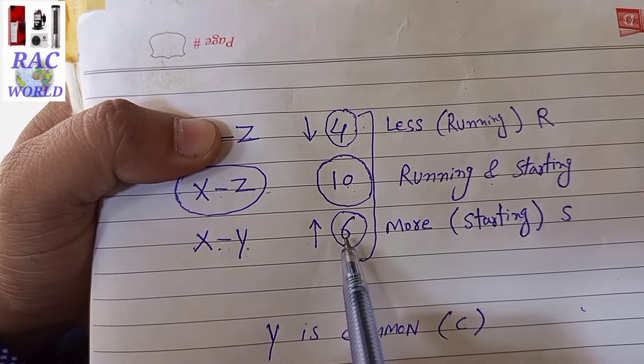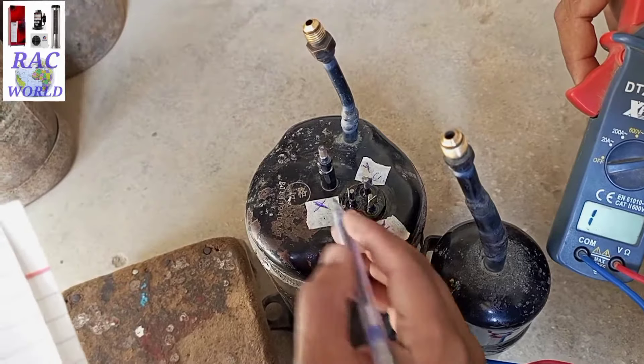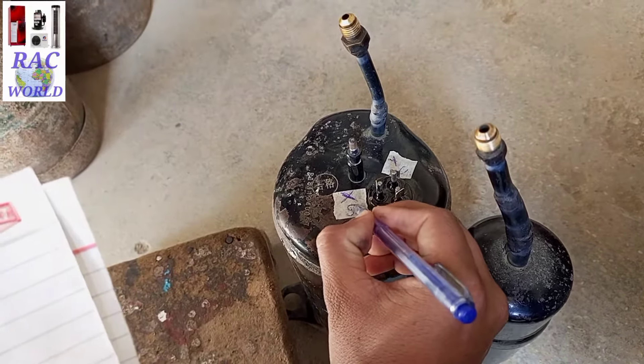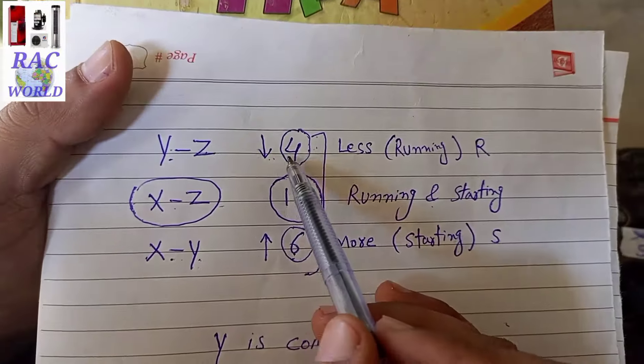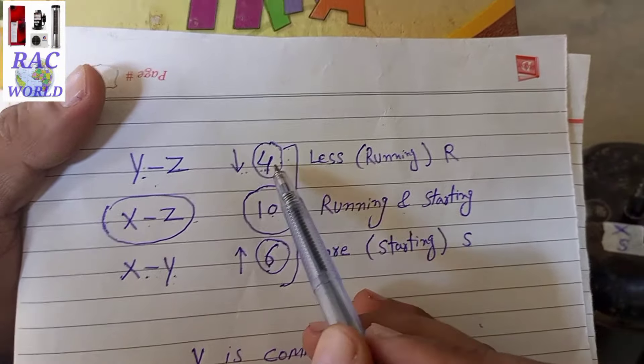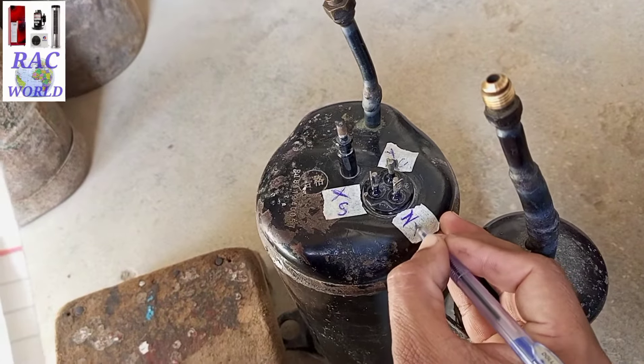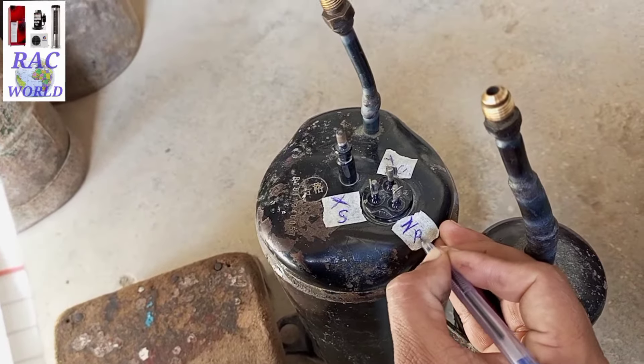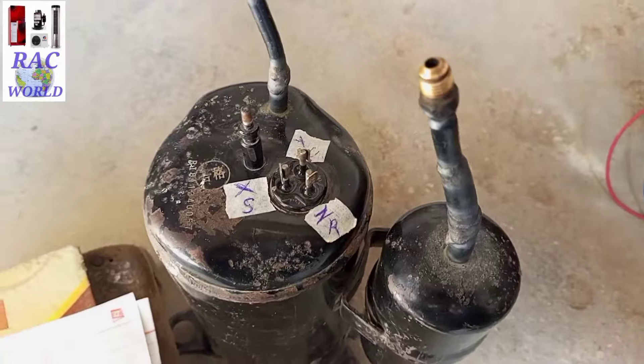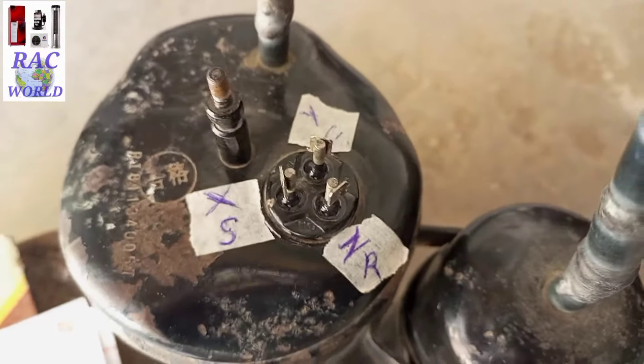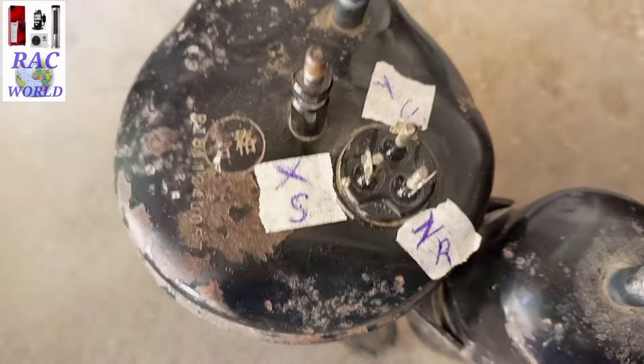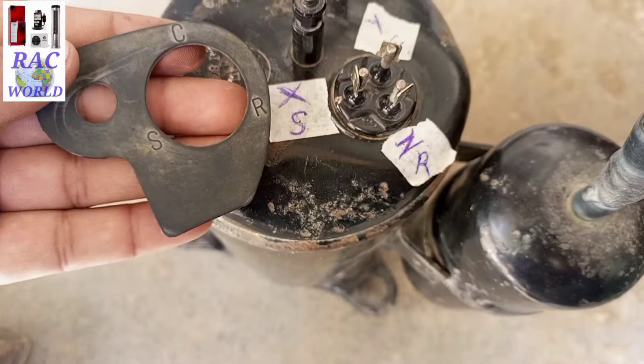So X is our starting point and Z is our running terminal. I will write 'S' for X and 'R' for Z on the compressor. To summarize: Y is our common, Z is our running, and X is our starting. Now I am going to verify this by matching with the rubber seal label provided by the company.